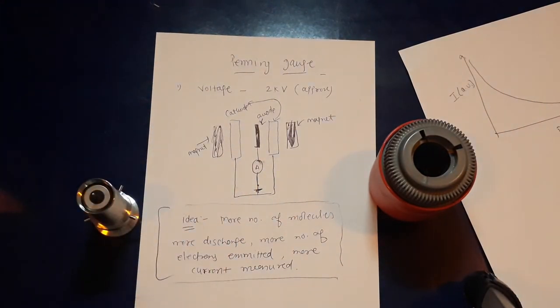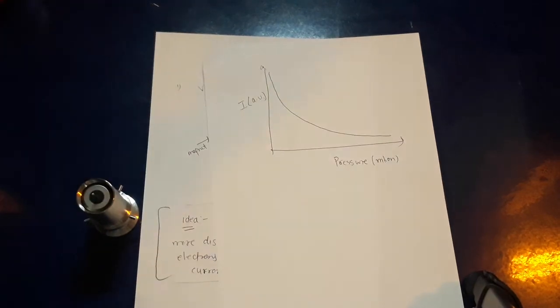When you have a large number of molecules, you have bad pressure. Large number of molecules means more discharge, more ions, that means more current. At higher pressure, very bad vacuum, you will have a large amount of current. That's why it is not recommended to use this gauge at higher pressure. Always recommended to use below 10^-2 millibar.